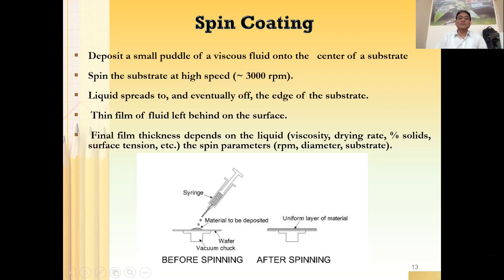This is the equipment which we are using in our laboratory. There are different companies and different makes. This is an Apex make spin coater. Here you can see you have to remove this, and then you can see the chuck. It is connected to the vacuum pump. You have to switch on the vacuum pump, and then you put your substrate inside, put a drop of that liquid, close this lid, and then the RPM and other parameters can be set here. Once you start it, deposition time also can be set, whether you want to rotate this for 5 minutes, 10 minutes, 20 minutes, whatever, right? Then again, there are many other parameters which need to be set if you really want to have a good quality thin film from the spin coating system.